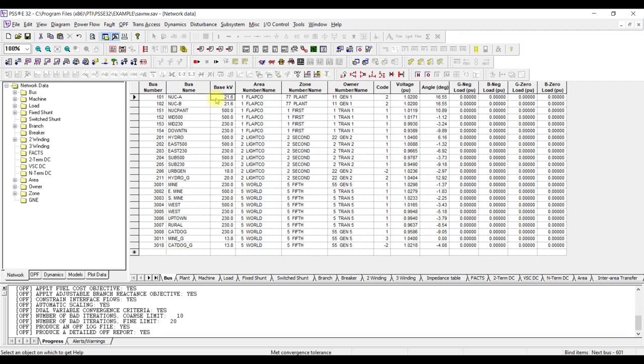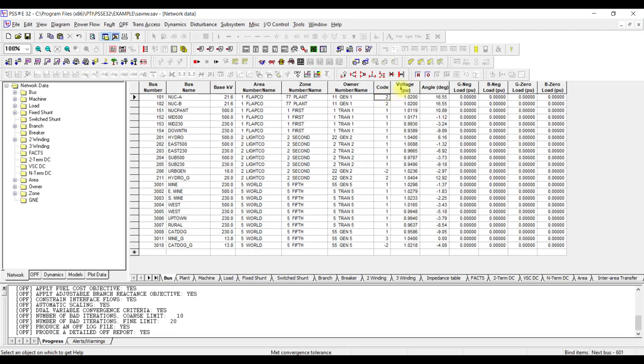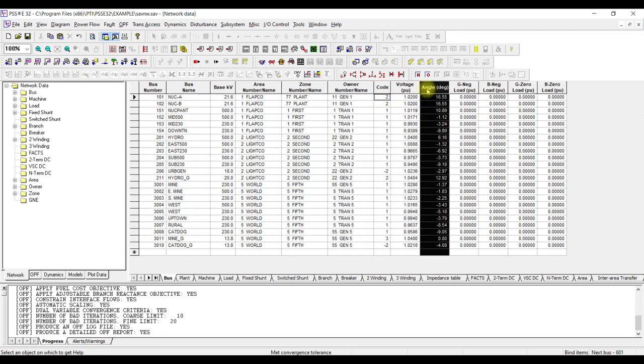Then you have to provide the base voltages — the same base voltages we discussed earlier. The voltage levels at different voltage levels are given here for different kinds of buses. If you are performing load flow, each bus or substation can belong to a different area, a different zone, or a different owner, and you can specify that here. The voltage and angle (delta) calculated by PSS/E will appear in the corresponding columns.